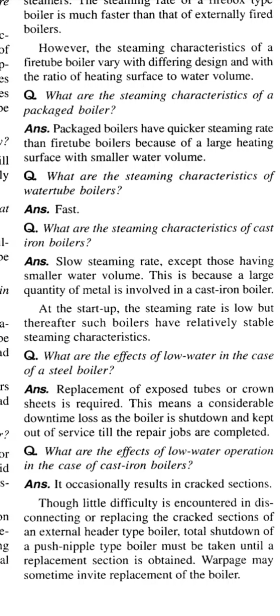Question: what are the effects of low water in the case of a steel boiler? Answer: replacement of exposed tubes or crown sheets is required. This means a considerable downtime loss as the boiler is shut down and kept out of service until the repair jobs are completed.